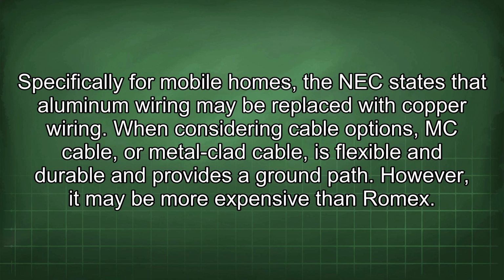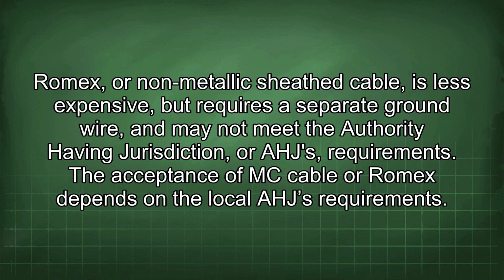When considering cable options, MC cable, or metal-clad cable, is flexible and durable and provides a ground path. However, it may be more expensive than Romex. Romex, or non-metallic sheath cable, is less expensive but requires a separate ground wire and may not meet the authority having jurisdiction, or AHJ, requirements. The acceptance of MC cable or Romex depends on the local AHJ requirements.